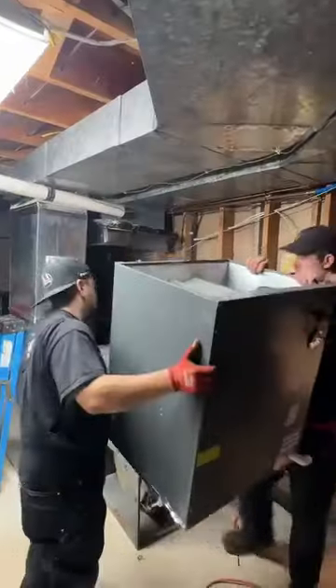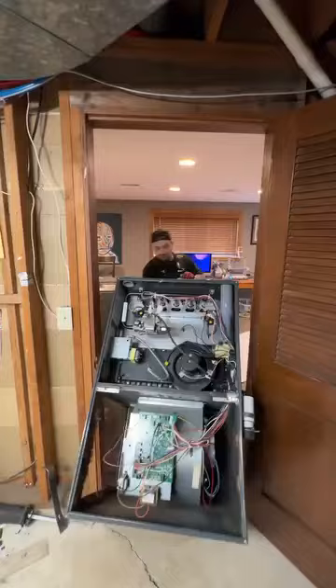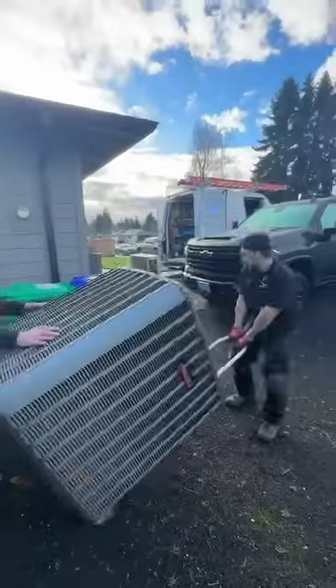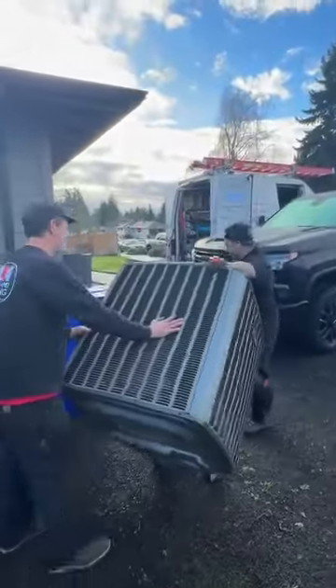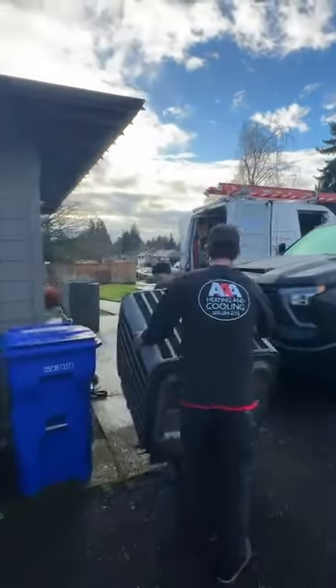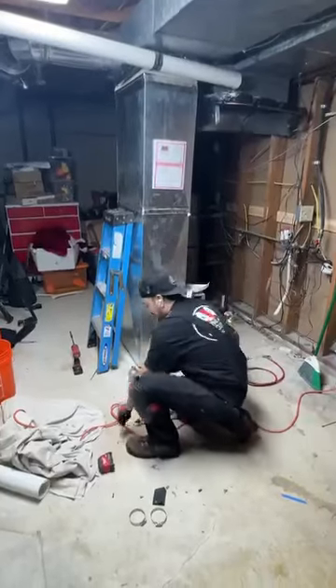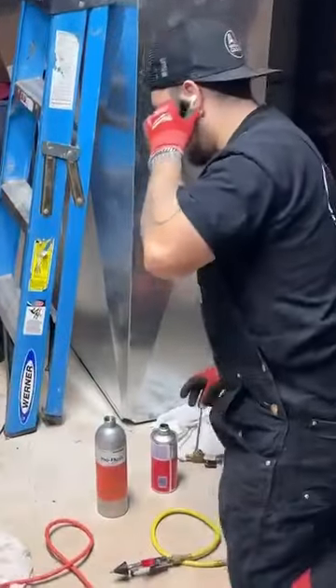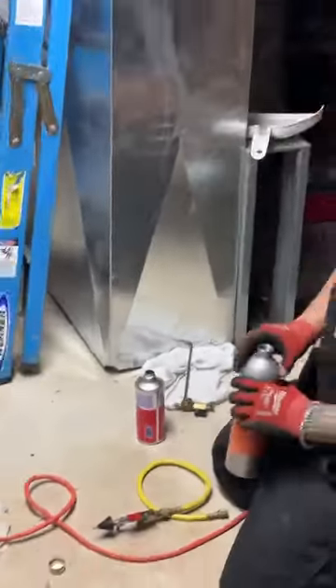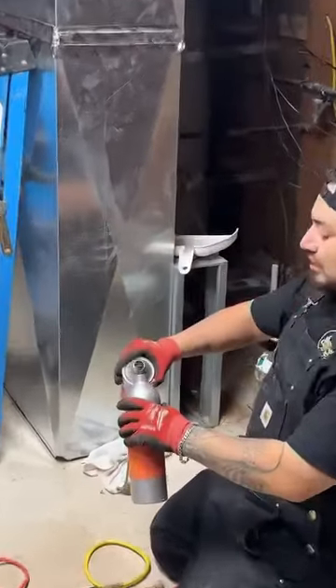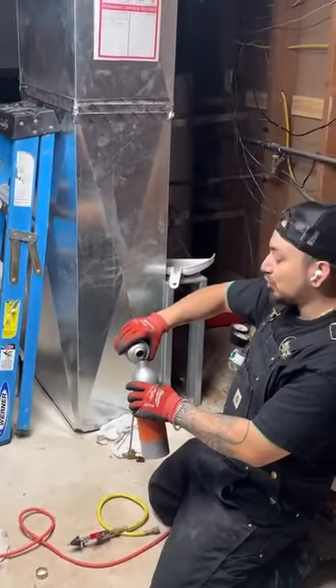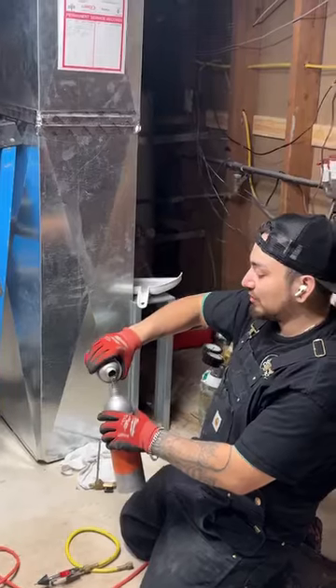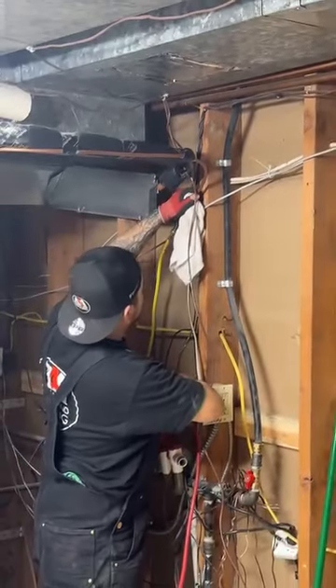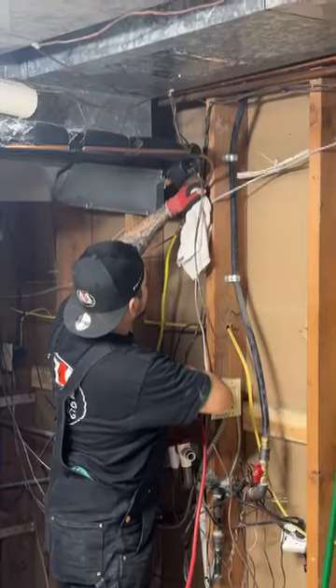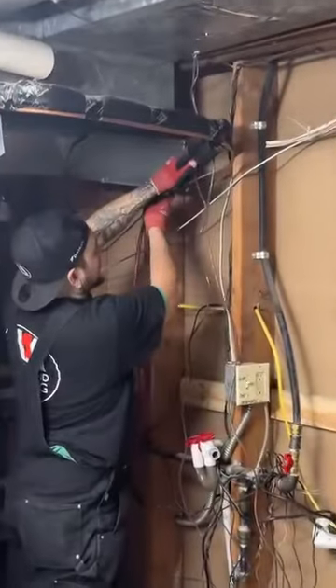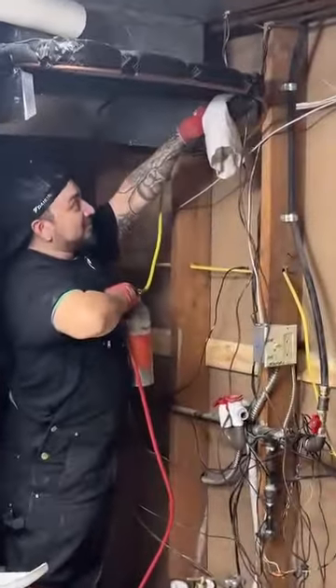Now, with everything detached from the original unit, we remove the old furnace unit from the home to be hauled away. With the outdoor heat pump unit now also completely drained of refrigerant, it is also ready to be hauled away. Next, we do a final cleaning step to remove any possibilities of the old refrigerant oil or other contaminants getting into the new system, preventing the contamination of the new refrigerant oil being added into the system. We also pressurize the air and perform an acid flush during this step of the install. We hit it with a dry blast as well to really ensure the line is as dry and clean as possible.